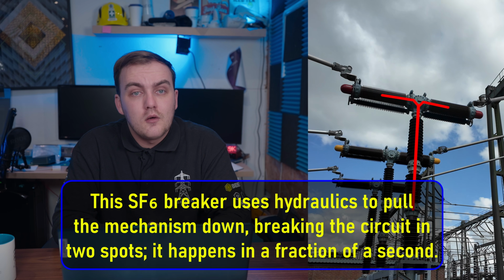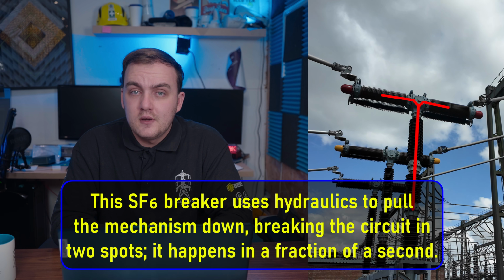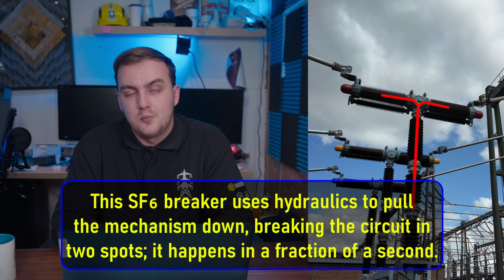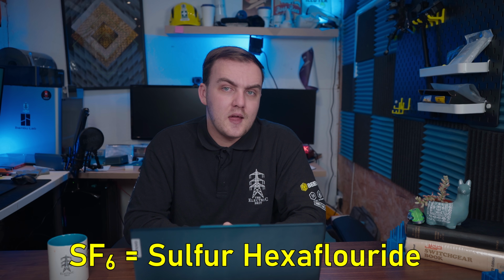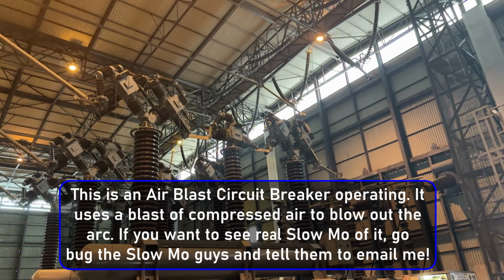So to do that, we need to separate the contacts really fast, like with a hydraulic or spring mechanism, and have something to extinguish or quench the arc that forms, like an insulating gas, such as SF6, or in this case oil, which fills the gap, blocks the arc and keeps everything cool, because these arcs are usually hotter than the surface of the sun.